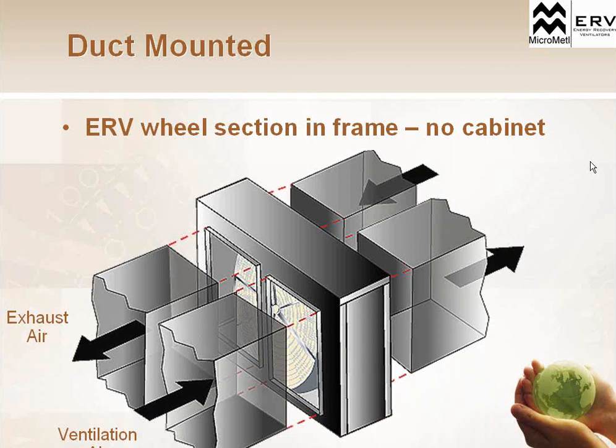If we are duct mounting the ERV unit, as I said, we can put it in a packaged outside system. We can put it indoors, duct mounted, air handlers, things like that. The ERV wheel section in the frame would be all that you're selecting. So you would actually have this frame box with the wheel inside, and you would mate your 2 or 4 airflows here, your supply connections and your return connections.